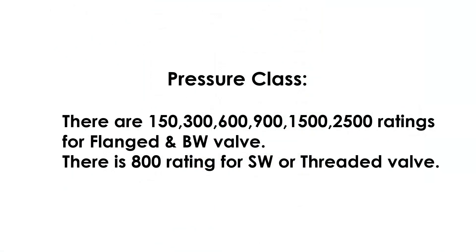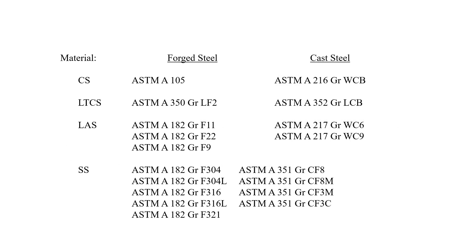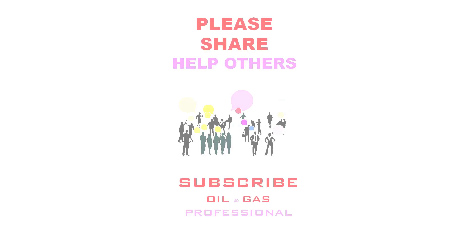Pressure classes for globe valves: there are 150, 300, 600, 900, 1500, and 2500 ratings for flanged and butt-weld valves. There is an 800 rating for socket-weld and threaded valves. For globe valve materials, please refer to the table showing the 800 rating and other details.